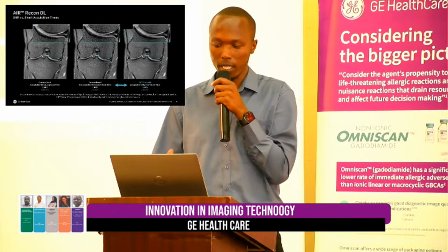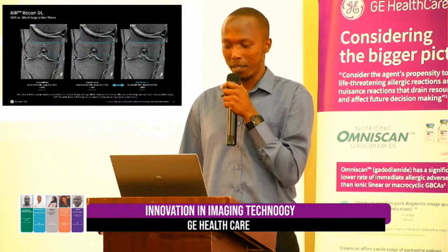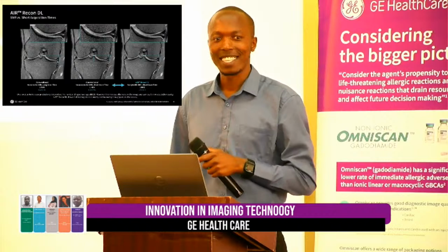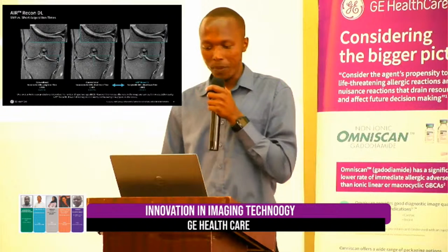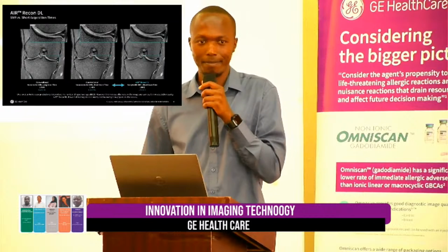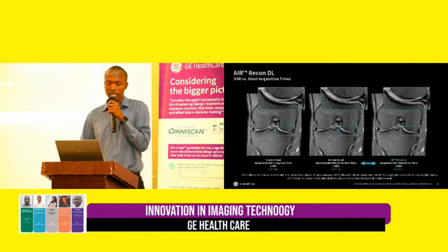Let's say you want to decrease the scan time using the NEX or any other parameter. Right now the image is acceptable, but it's at 3 minutes and 24 seconds. And you know we are scanning multiple planes, multiple contrasts, so the cumulative time will be very long.